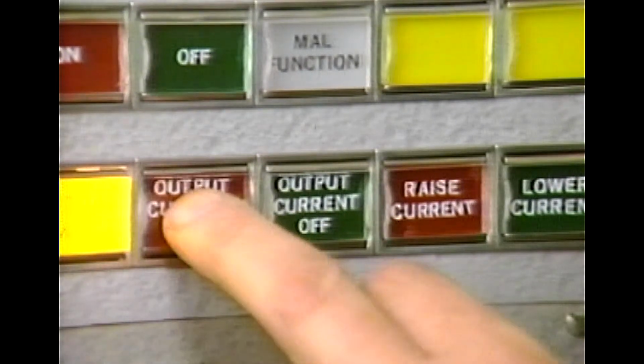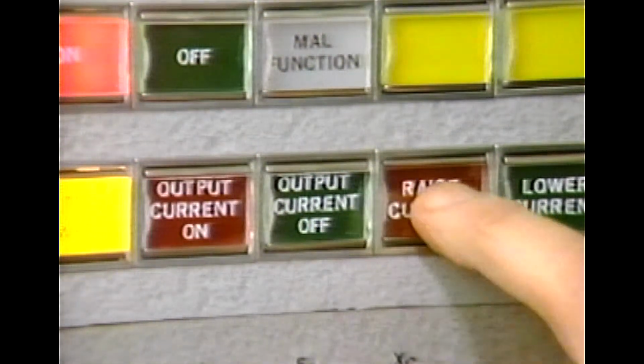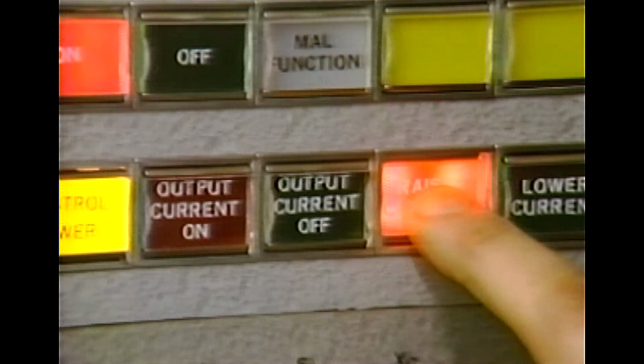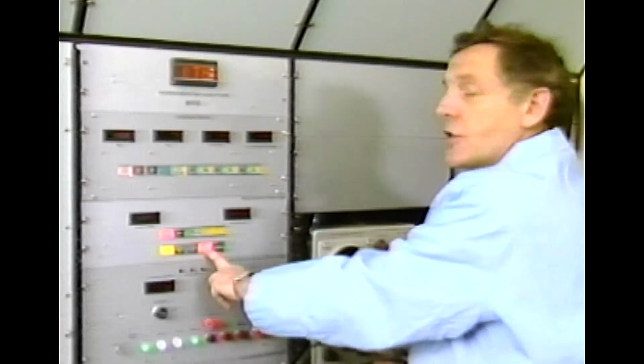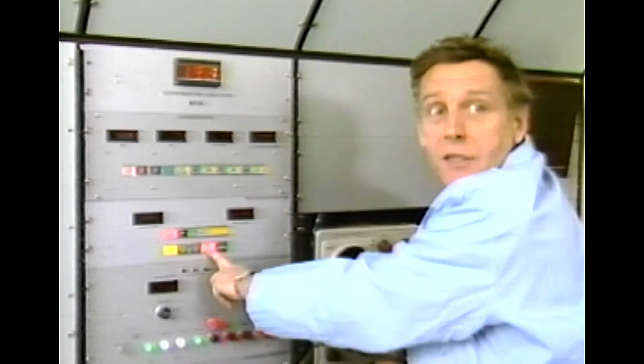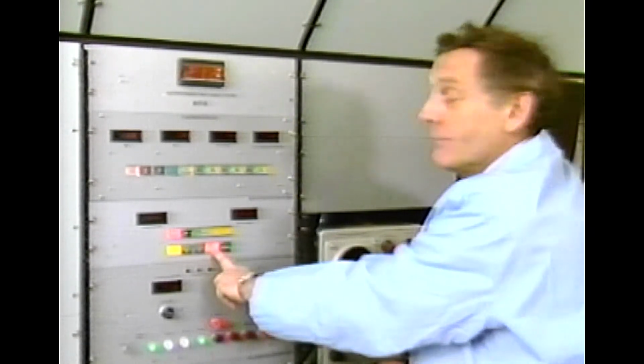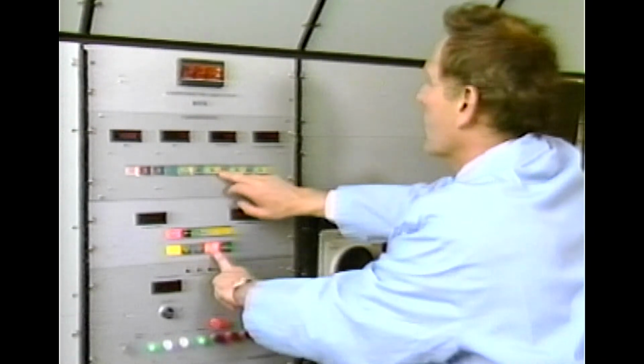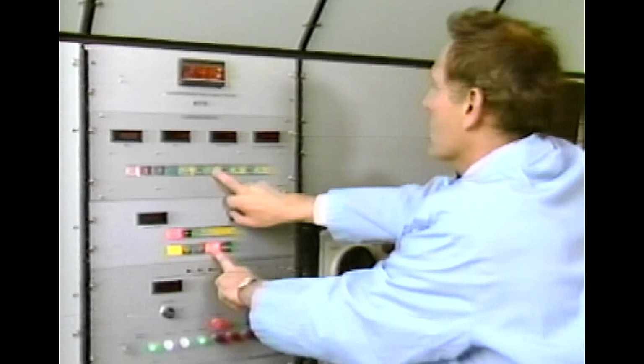Okay, check the partial discharge on the storage scope bridge. Performance looks good, so current is applied at the same time as voltage. Slowly, the level is raised to 4100 amps, corresponding to 333 MVA on each cable, or 1000 MVA three-phase, the design goal for continuous steady-state operation of the superconducting cables.